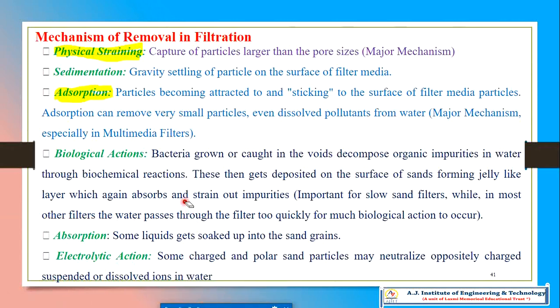Another important process is called adsorption. Particles become attached and stick to the surface of the filter media. Adsorption can remove very small particles, even dissolved pollutants, from the water. It is a major mechanism, especially in multimedia filters.